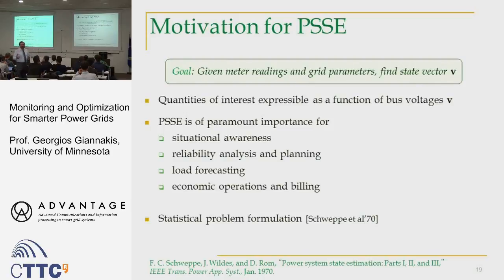Of course, you cannot have a voltage meter everywhere, right? It is very important for situation awareness, for reliability analysis and planning, and also for load forecasting, because if I know the voltages there, even without measurements, using the power flow equation in reverse, I can tell you how much power is going to be needed there.